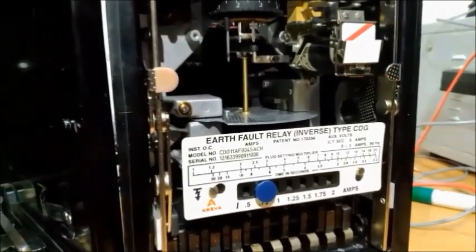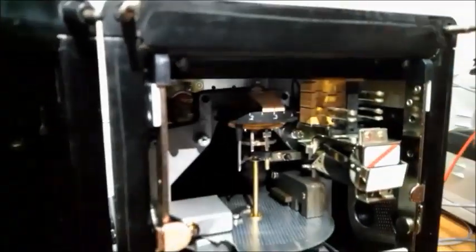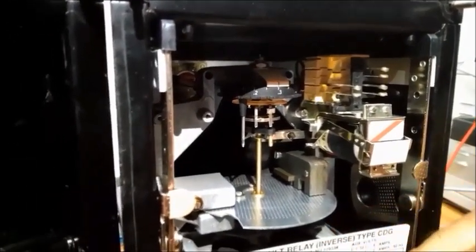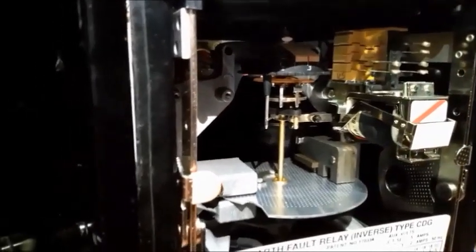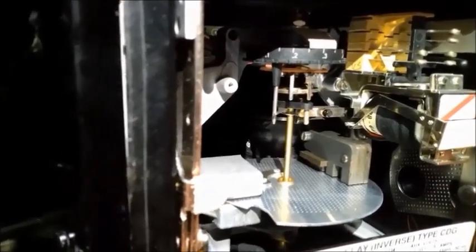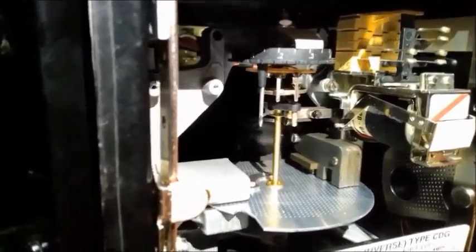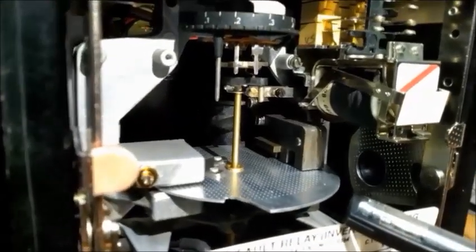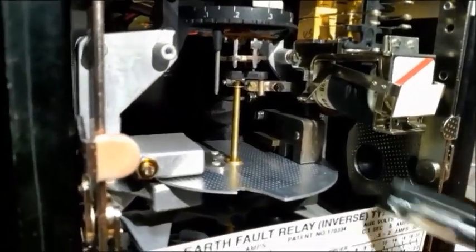That is 0.75. So now you can see closely. Pickup current is when the disk is start rotating. Just try to start rotating. That is our pickup current. So we just inject our 0.75 set current. So we are now injecting 0.75 amps slowly. Increase. 0.75. Now you see the disk. You see here, the disk is slowly rotating. That means we got our pickup current. So now stop.